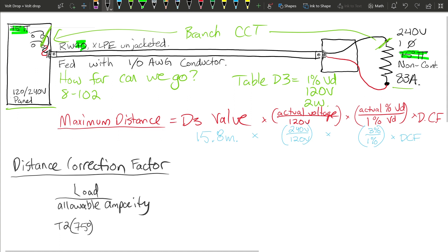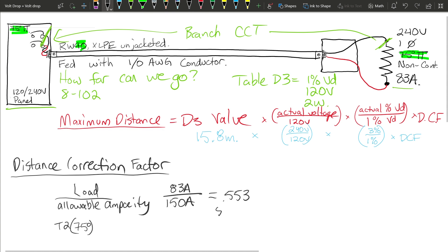The load is 83 amps compared to the 150 amps allowable ampacity from Table 2's 75 degree column. Dividing 83 by 150 gives approximately 0.553 — meaning we are loading this conductor to about 55.3% of its allowable ampacity.